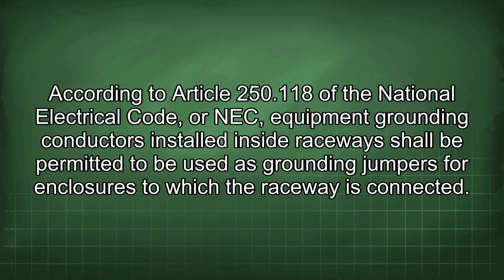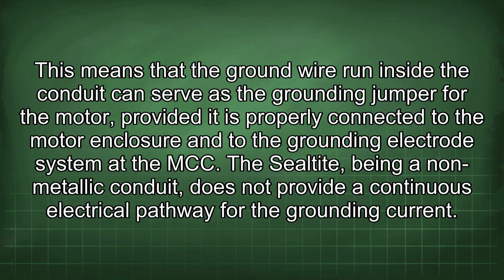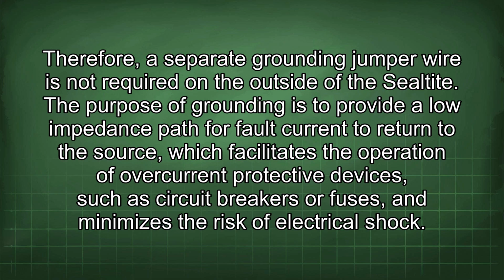According to Article 250.118 of the National Electrical Code, or NEC, equipment grounding conductors installed inside raceways shall be permitted to be used as grounding jumpers for enclosures to which the raceway is connected. This means that the ground wire run inside the conduit can serve as the grounding jumper for the motor, provided it is properly connected to the motor enclosure and to the grounding electrode system at the MCC. The Sealtite, being a non-metallic conduit, does not provide a continuous electrical pathway for the grounding current. Therefore, a separate grounding jumper wire is not required on the outside of the Sealtite.